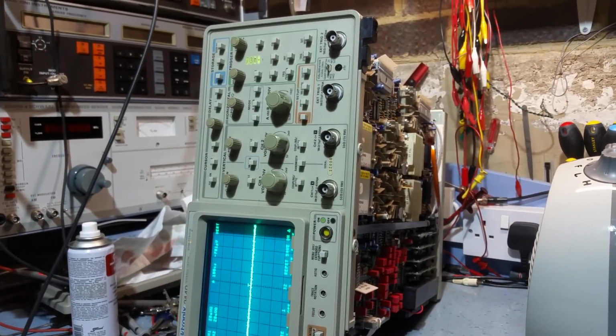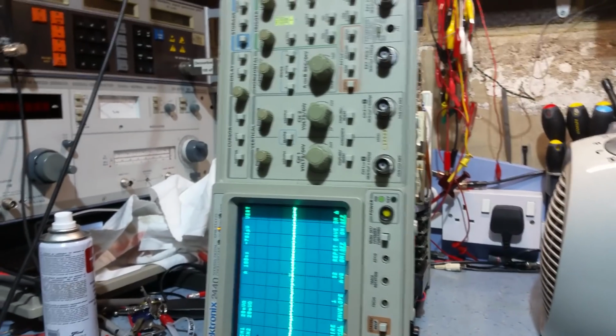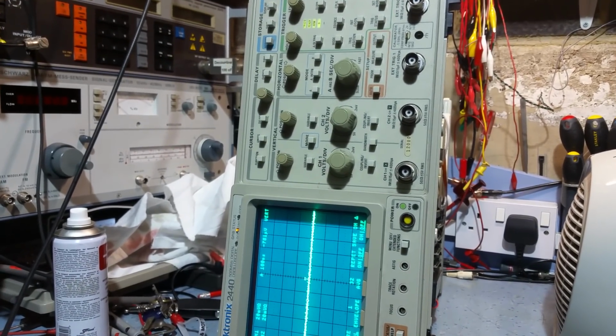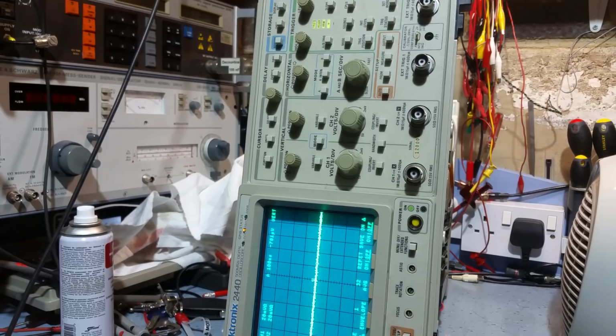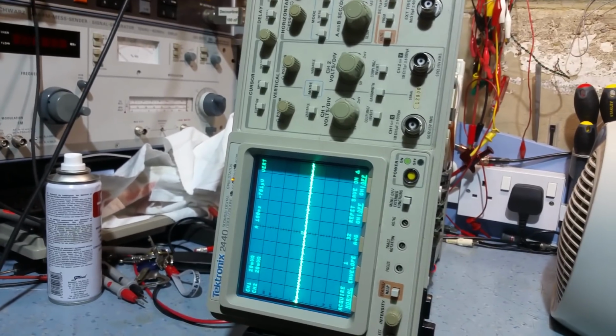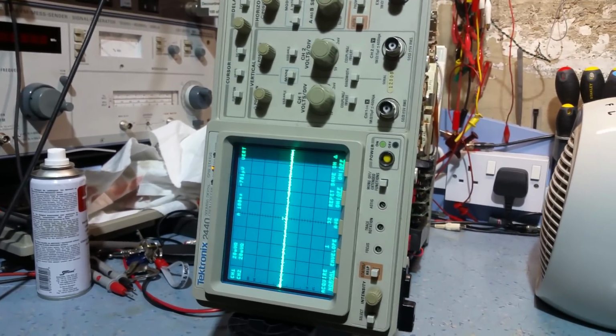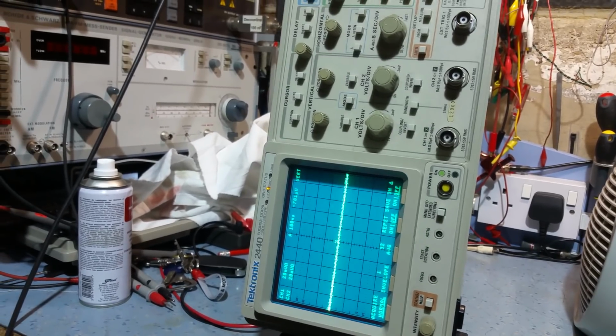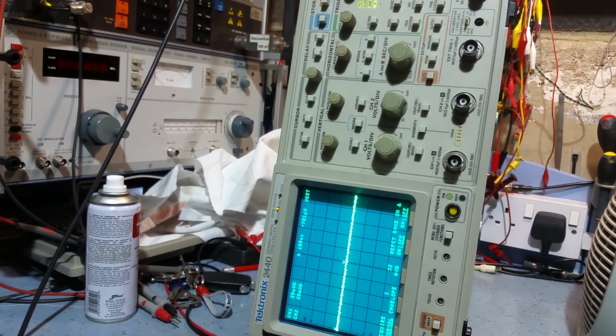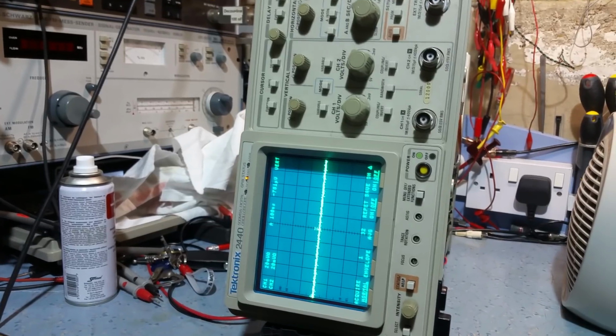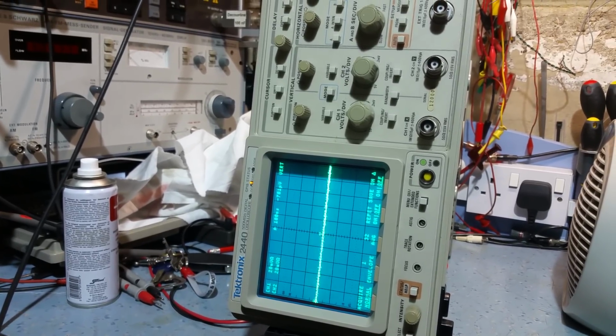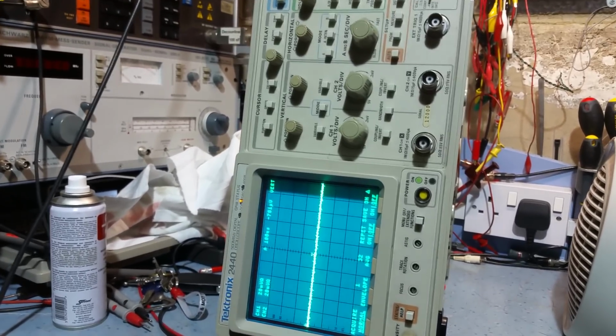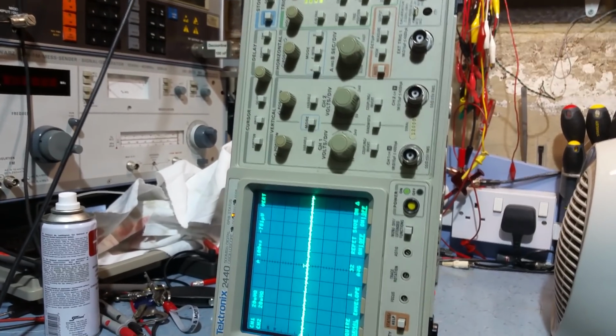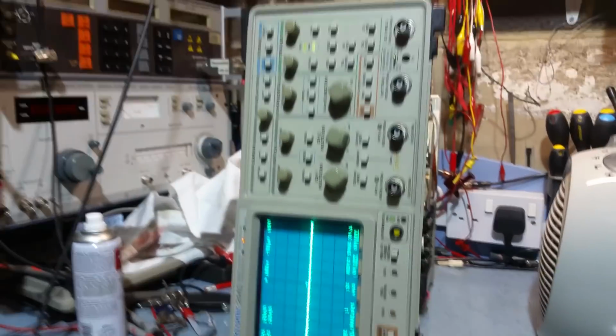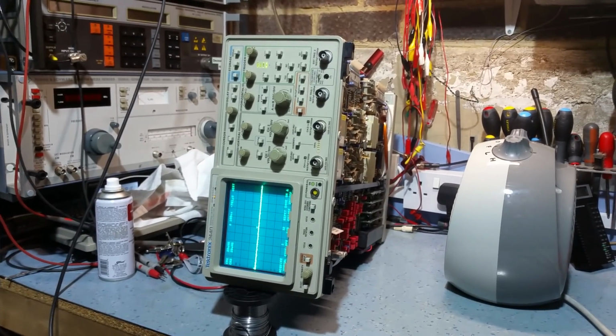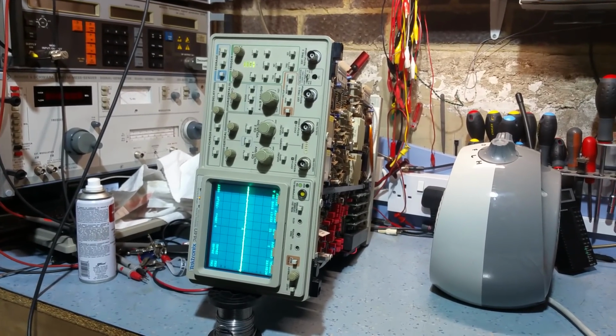The battery is from 1989, 1990. So hopefully, to avoid losing calibration, I'll jumper it across my power supply to keep the supply up whilst I change the battery. You can actually change the battery and not lose the calibration if you're quick, because there is a diode and a capacitor across there, so the capacitor will hold up for as long as you're fairly quick. I think you've got about 20 minutes or so. It shouldn't take me that long to change it. So at the moment it's working. I'm going to pop it back in its box and we'll run it through a few tests.